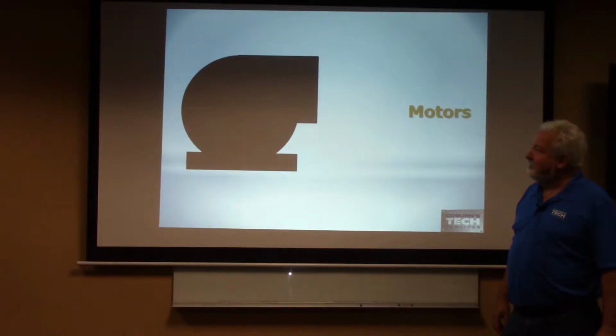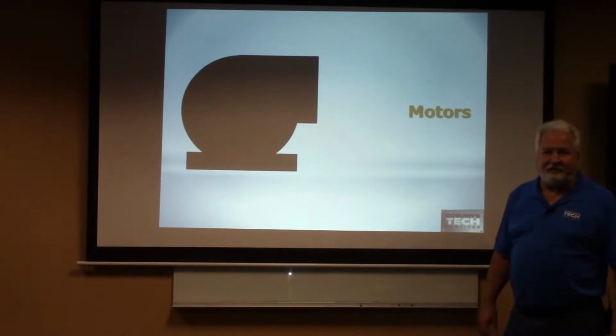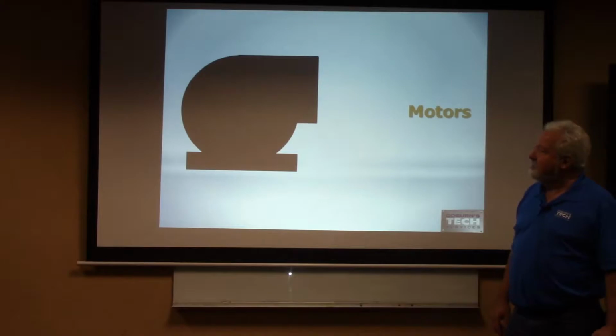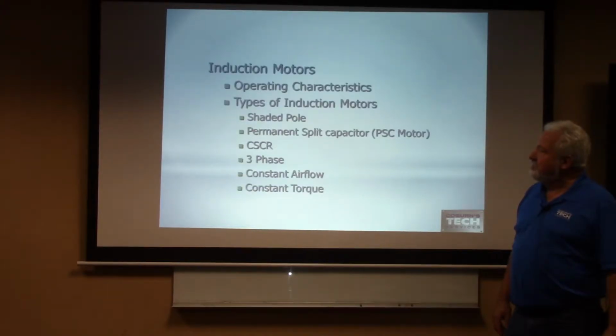Okay. Let's look at motors a little bit. I think motors are going to be something that we need to pay attention to. We have induction motors, which is typically what we're going to be dealing with out there in the industry. We're going to look at the operating characteristics and types of induction motors: shaded pole, permanent split capacitor motors, CSCR motors, 3-phase motors, constant airflow and constant torque motors.